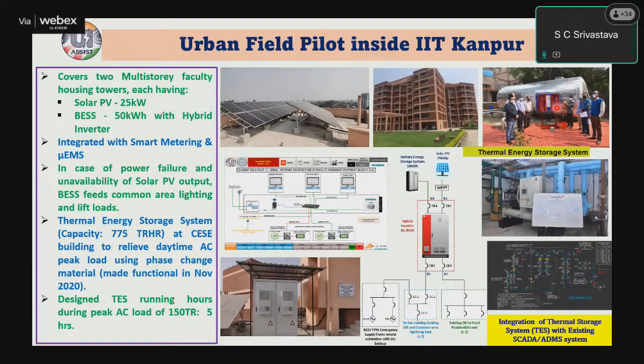Thermal energy storage operates with a glycol solution with phase change material inside, and it is connected to the chiller plant, the main chiller plant in the building. The idea is that during night time when load is not there, it will take chilled water and bring down the temperature to -6 or -10 degrees Celsius, and then during daytime it supports the air conditioning.